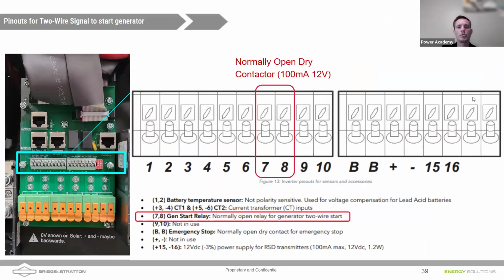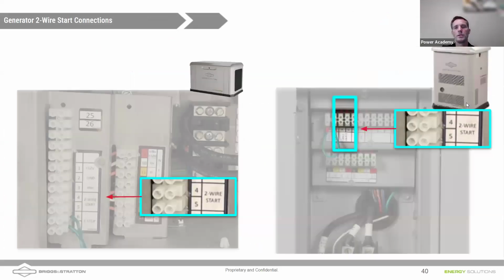All right, so to hook up the 2-wire start on the generator, you use pins 7 and 8. That's a normally open relay, and when it calls for the generator, it would close those 2 pins, and those are pins 4 and 5 on our generator controllers to enable 2-wire start.